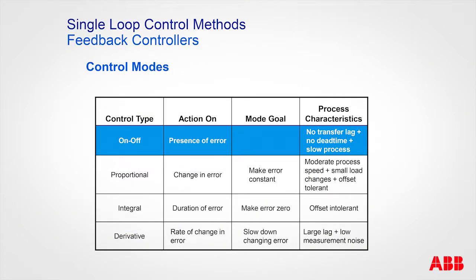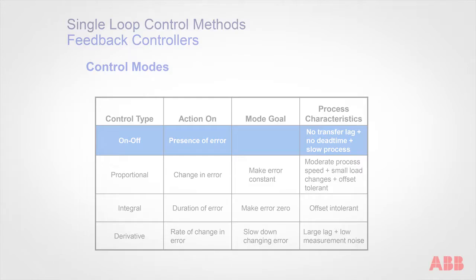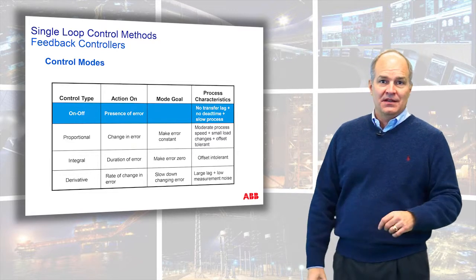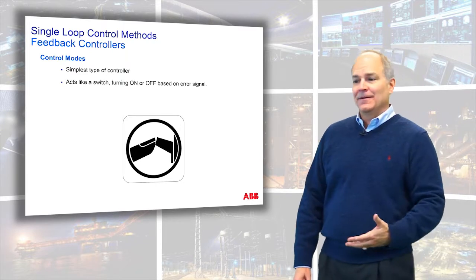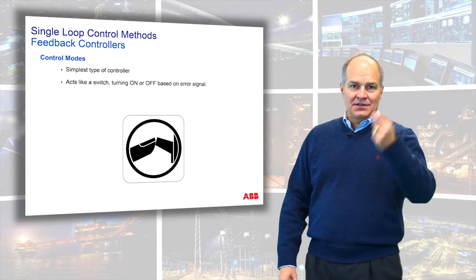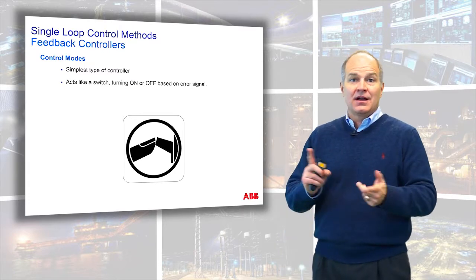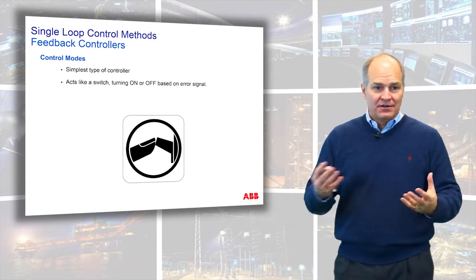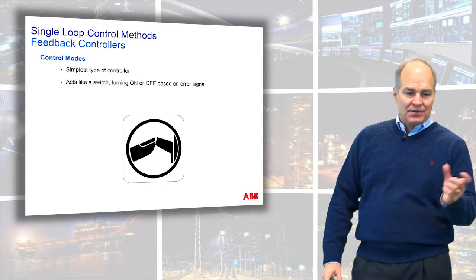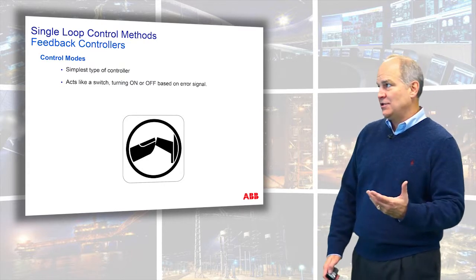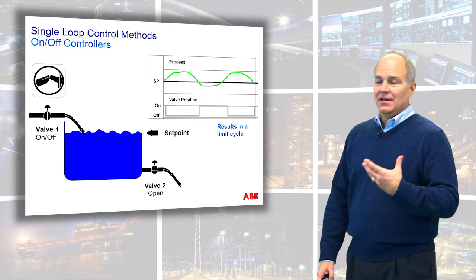The on-off controller type is basically like a light switch — it's either on or it's off — or a relay, either open or closed. It operates off the presence of error: whether the error is large or small, you're at 100% or 0% of your valve. So on-off control is a very simple two-mode kind of output, and it's usually used in very large vessels where the dynamics are very, very slow.